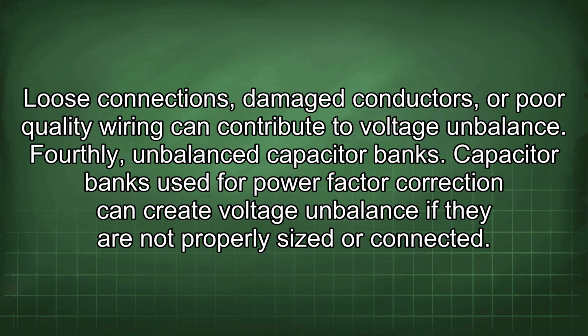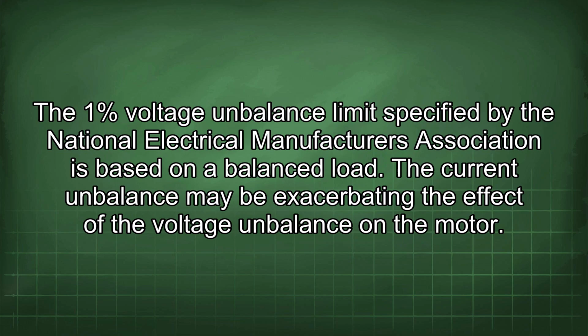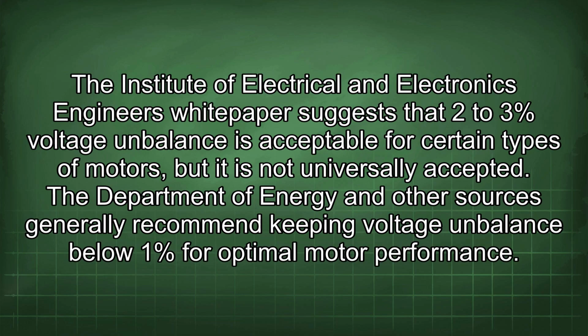sized or connected. The 1% voltage imbalance limit specified by the National Electrical Manufacturers Association is based on a balanced load. The current imbalance may be exacerbating the effect of the voltage imbalance on the motor. The Institute of Electrical and Electronics Engineers white paper suggests that 2 to 3% voltage imbalance is acceptable for certain types of motors, but it is not universally accepted. The Department of Energy and other sources generally recommend keeping voltage imbalance below 1% for optimal motor performance.